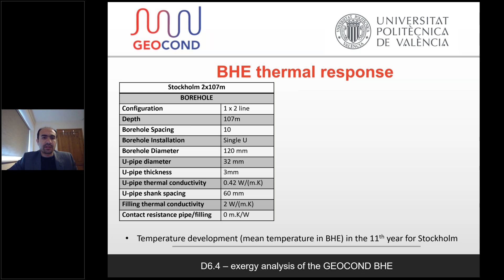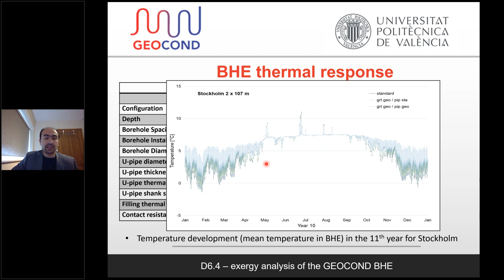Let me use the laser pointer to indicate something. We have three profiles here: the standard case, the GeoCOND grout with standard pipe, and the full GeoCOND case. The lightest color corresponds to the full GeoCOND case, whereas the darkest corresponds to the standard case. From this figure, we can see that for the full GeoCOND case, a higher temperature profile developed in the BHE. So it's a good visual representation that using the GeoCOND materials elevated the temperature developed within the fluid of the BHE, and that's basically why a greater amount of energy, or exergy, would be extracted from the BHE.